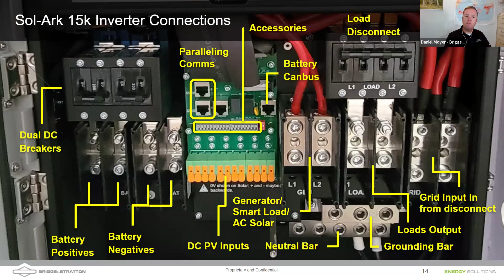And then on the left we have dual battery inputs. Now, Andrew, I really like this, is that there's 2 positives, 2 negatives. That allows us, if we have 2 stacks of SimpliPHI 6.6 batteries, we can bring those into a Sol-Ark without the need for an external bus bar. Again, making this install quicker, less expensive, less one box to hang on the wall. And you got the battery breakers there as well.